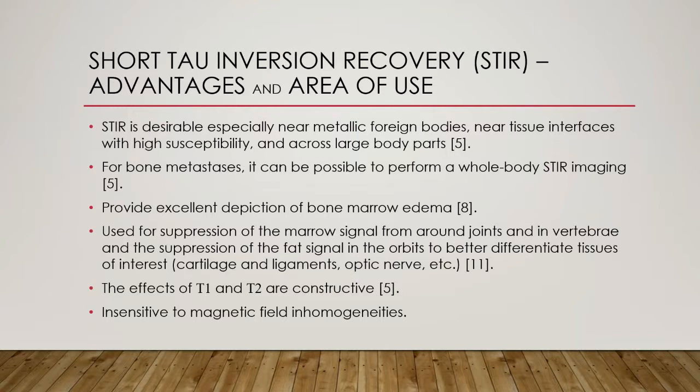In conventional T1-weighted spin echo imaging, tissues with long T1 and T2 have destructive effects on signals, but in STIR imaging the effects of T1 and T2 are constructive. This arises from the fact that the longitudinal magnetization of long T1 tissues in STIR remains inverted and produces a high signal. Also, STIR is insensitive to magnetic field inhomogeneities.